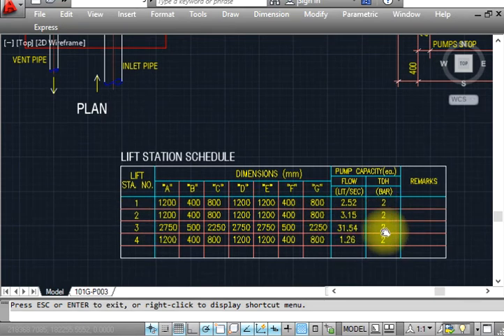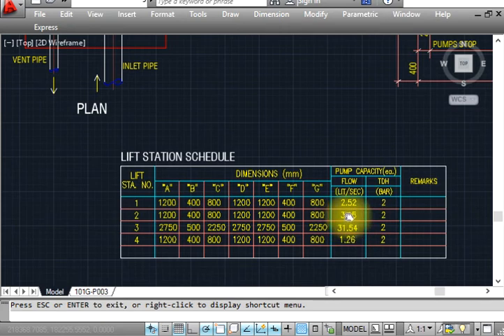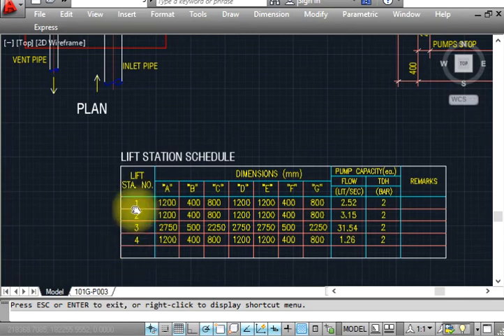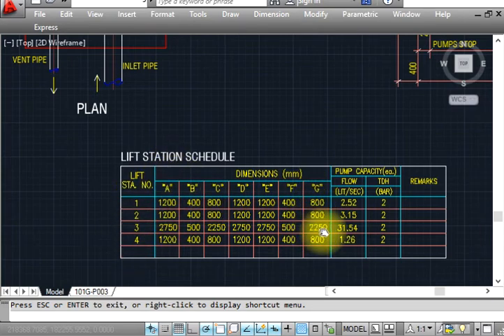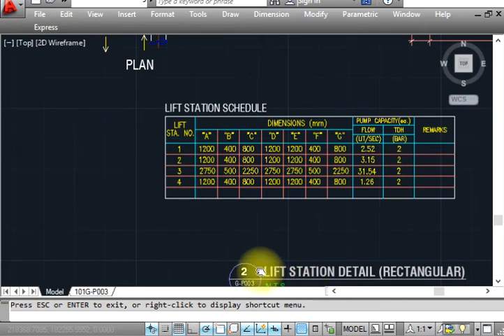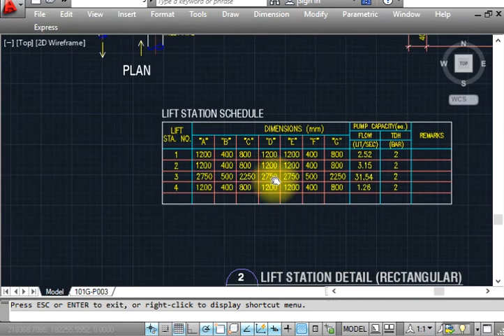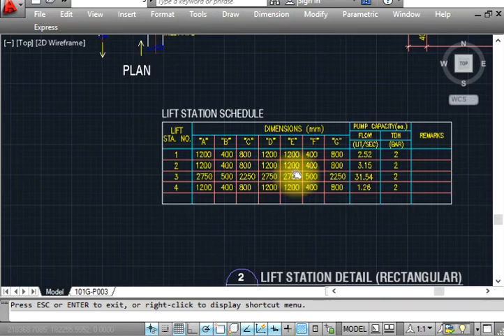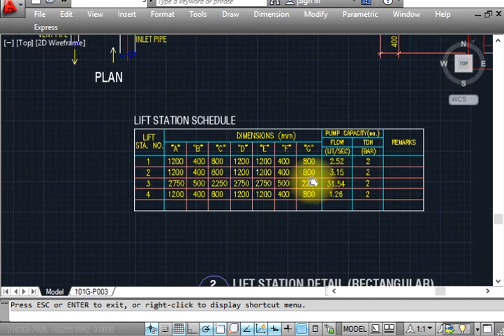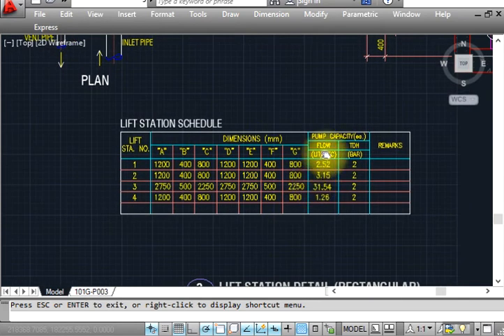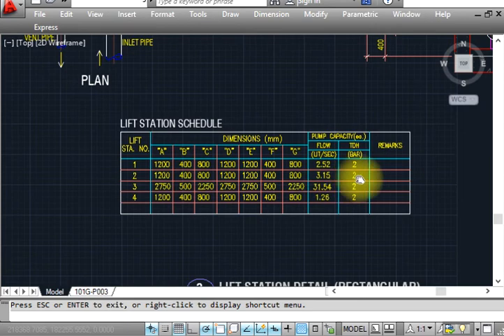This is 2 bar, or liters per second pump capacity needed. Because we have four lift stations, this schedule is made for four. This is lift station 2 - dimensions A is 1200, B is 400, C is 800, D is 1200, F is 1200, G is 800. This pump capacity we're using is 3.1 liters per second and 2 bar.